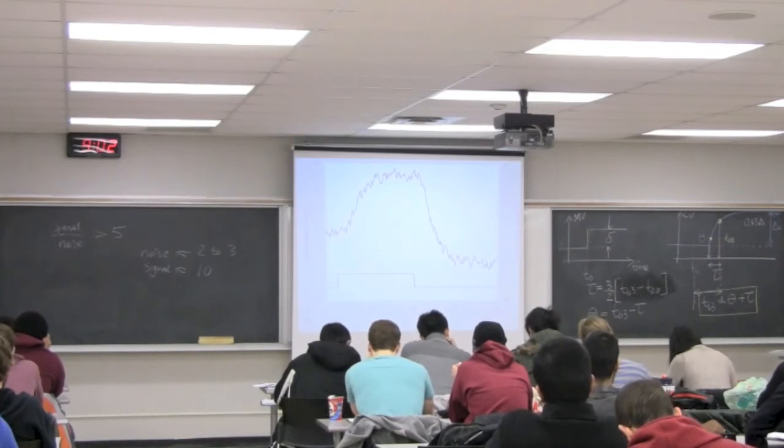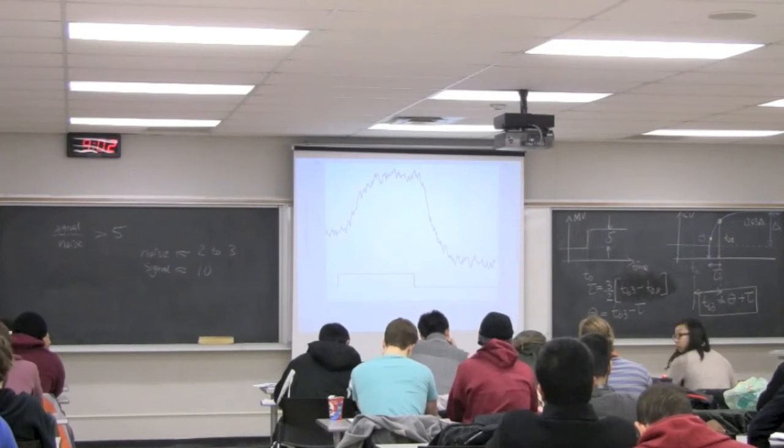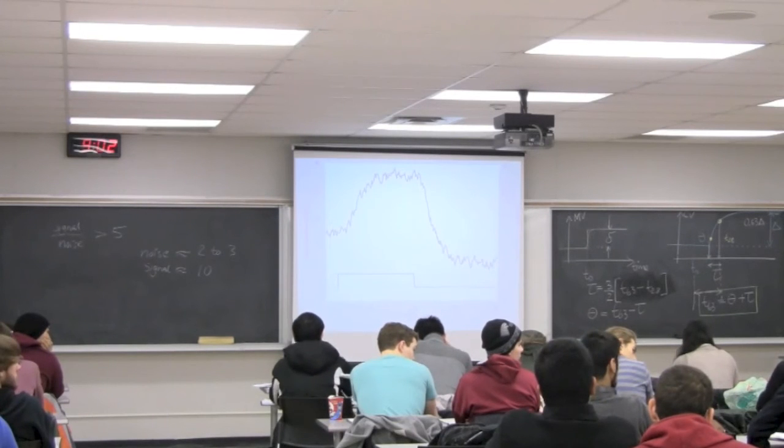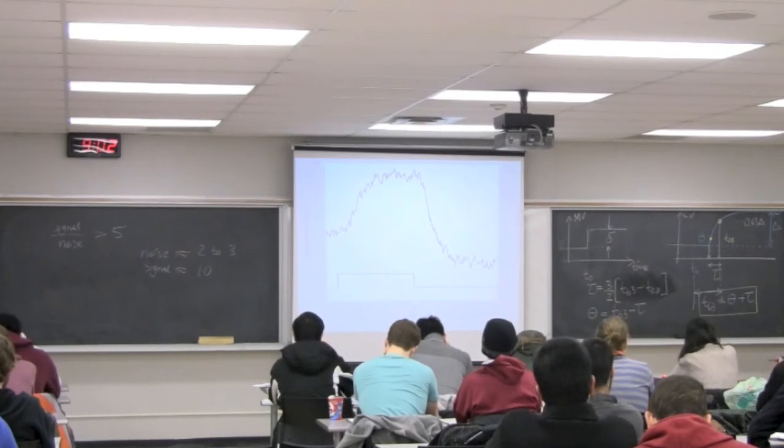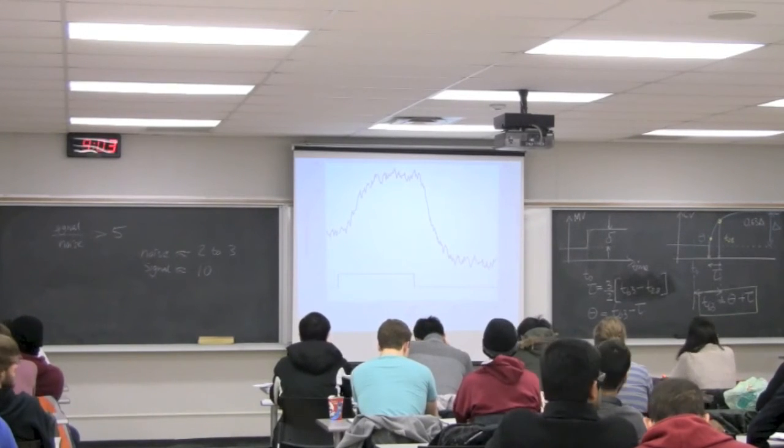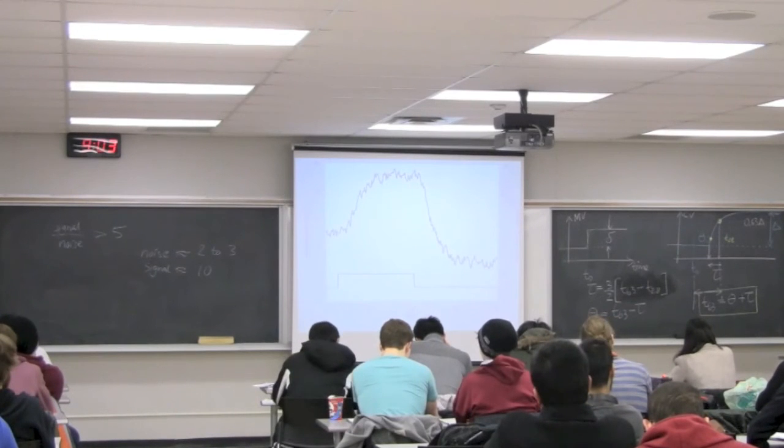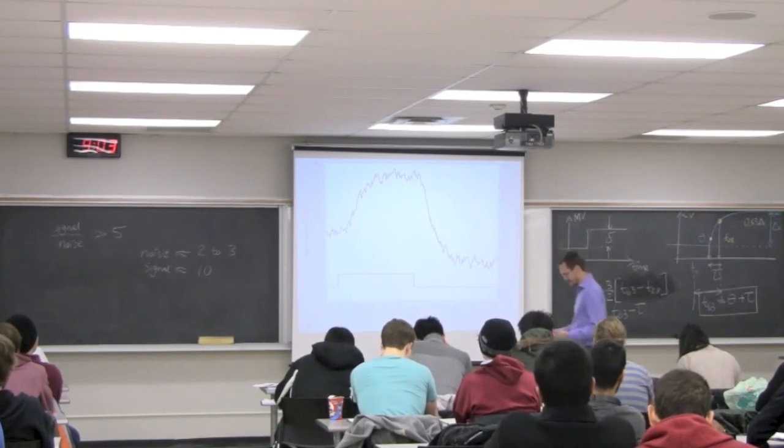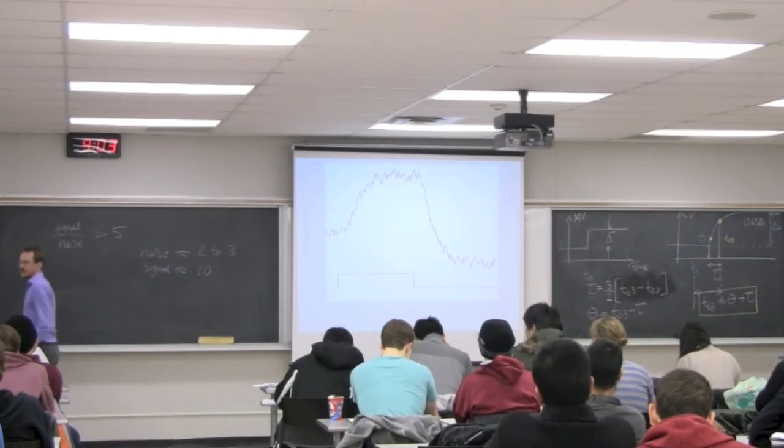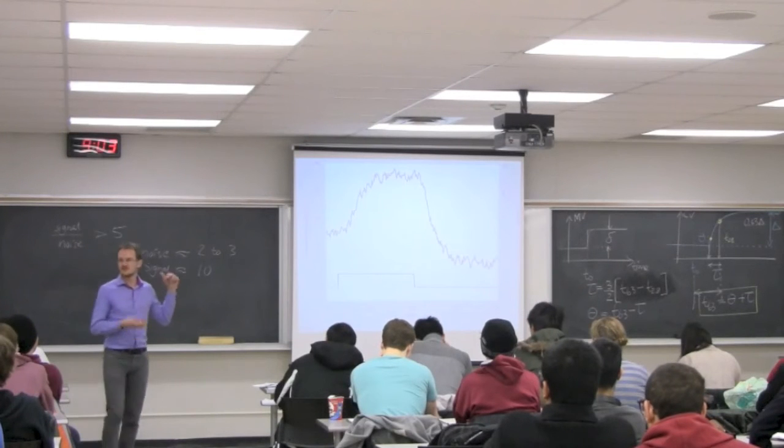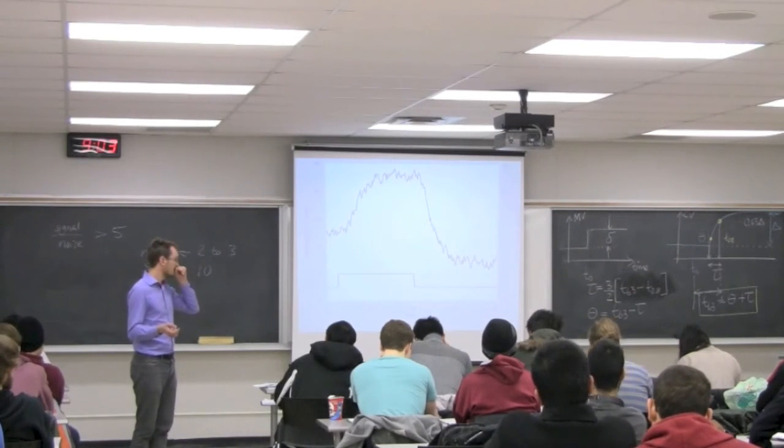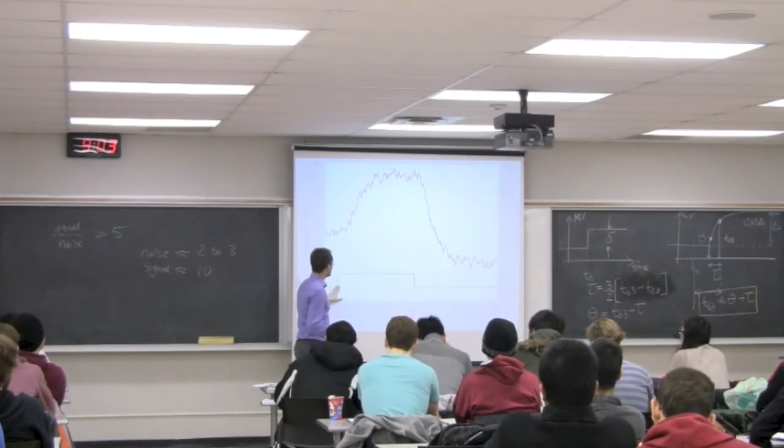This is reasonable values. You can locate T63 and T28 from this graph. If this step was shorter, let's say we didn't steady out at 84. Let's say we steadied out here at 78 degrees. We probably wouldn't be able to figure out where T63 and T28 are. That's where that rule of thumb comes from. But don't treat it as an absolute requirement. If your signal-to-noise is 4, go for it. You're not going to repeat your work. What's up with this one? Can we use this data? What's up with this data? I'm using it up until time 40. We can use it up until time 40. Everyone agree with that? Why can't we use it after time 40? What's bothering you about this plot? Something's bothering you? What's there that's not feeling right? We have two step inputs. So the data can overlap with the time delay.